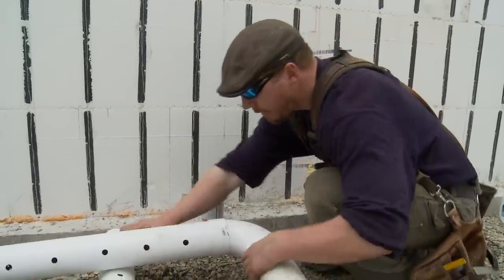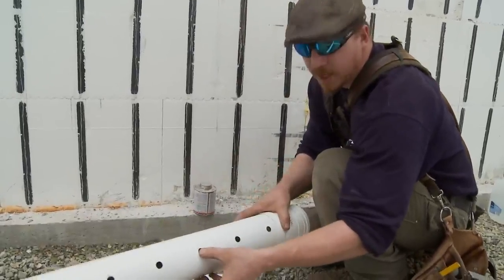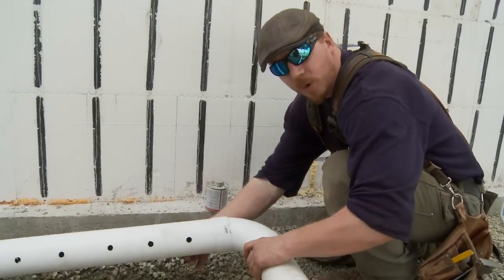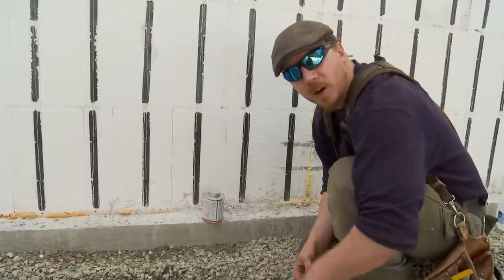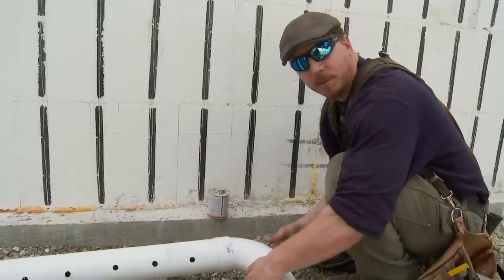When you're installing this pipe, a typical pipe has holes that are close to 90 degrees apart. It's generally a good idea to orient one set of holes straight down — that way if you should ever get any moisture inside this pipe you don't end up with standing water, which could plug the pipe and cause some issues with mold inside the pipe.